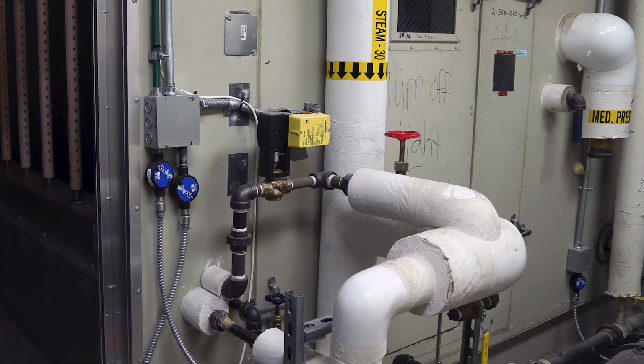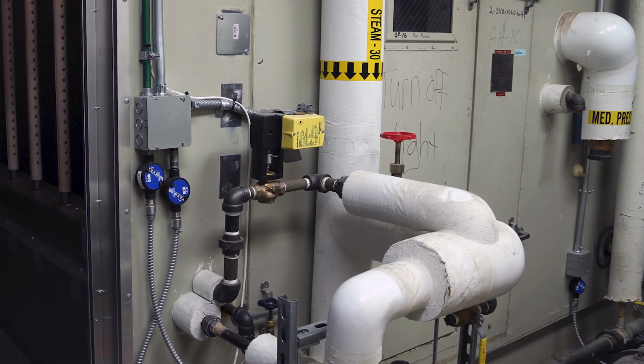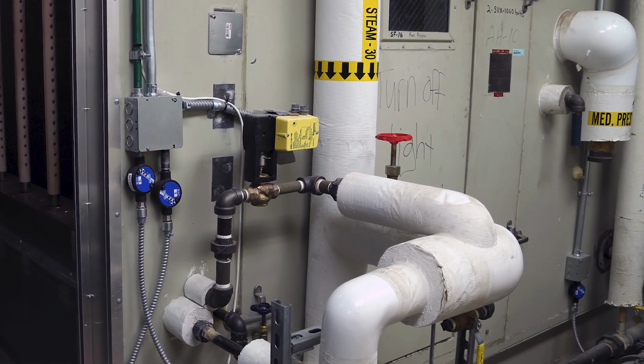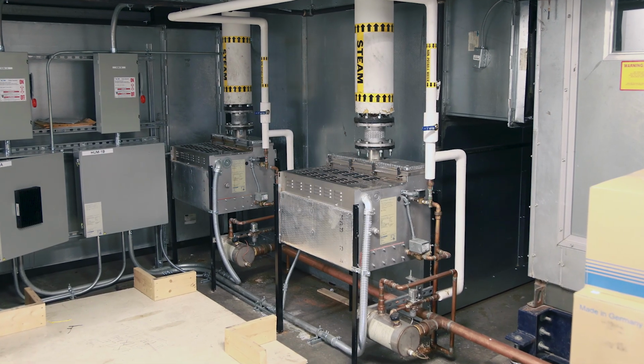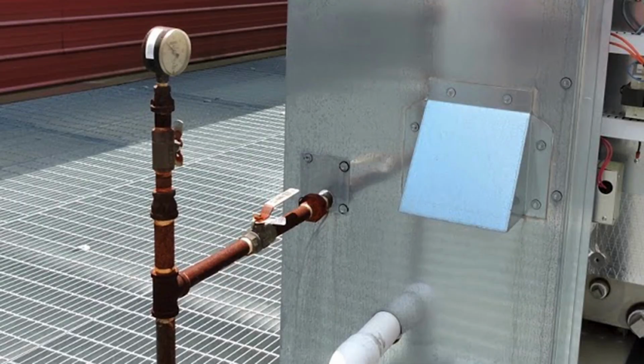And so I know in the last session we talked briefly about steam generation methods. How is a humidification system different when we're using a boiler or making steam elsewhere? And when should we be using each one? In general, I like to think of it as use whatever energy source is most readily available and cheapest to operate. If you already have steam available from a boiler and you can tap into it, well, why not? You don't have to make it because you've already got a device to do that. If you don't have that available, then you're forced to make the steam initially. And that can be done either with natural gas or electricity, or you can do it indirectly. Some way you've got to put all the energy into the water to cause the phase change.